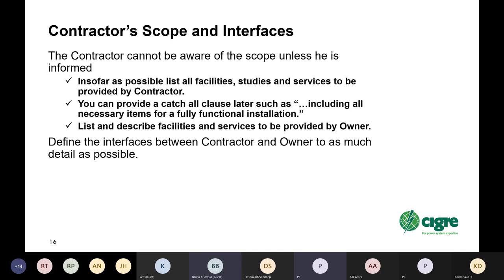You can always add a catch-all clause later, such as including all the necessary items for a fully functional installation. You should list and describe facilities and services to be provided by the owner. You should define all the interfaces between the contractor and the owner, and even interfaces between other contractors and the HVDC contractors, in as much detail as possible. The more information that you put into the specification in this regard, the fewer the opportunities for later disagreement and possible cost increases. And so it's highly recommended that you do a good job on defining the scope and the interfaces.